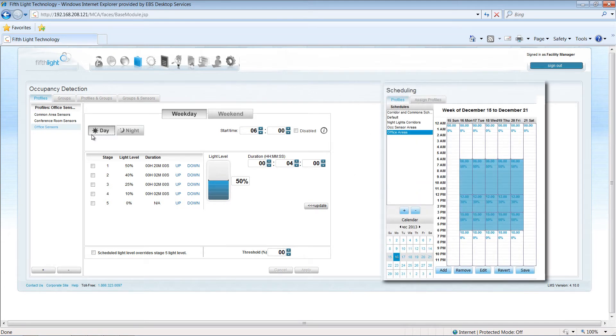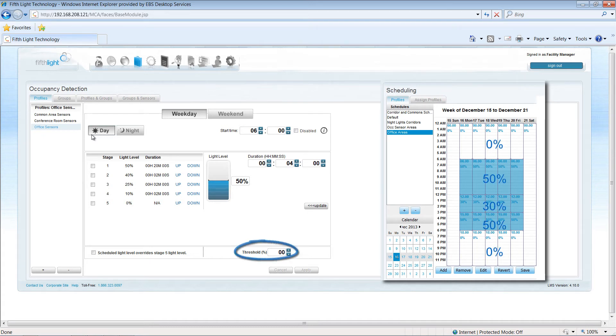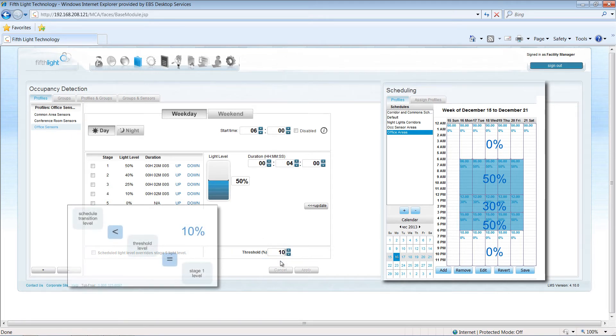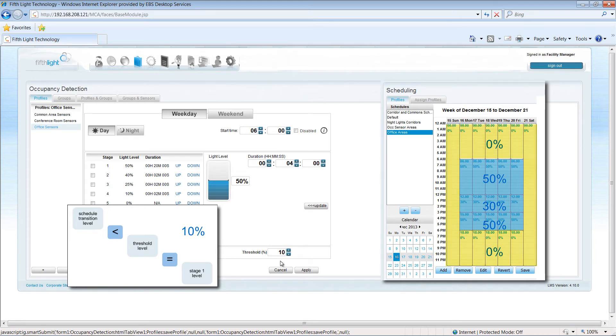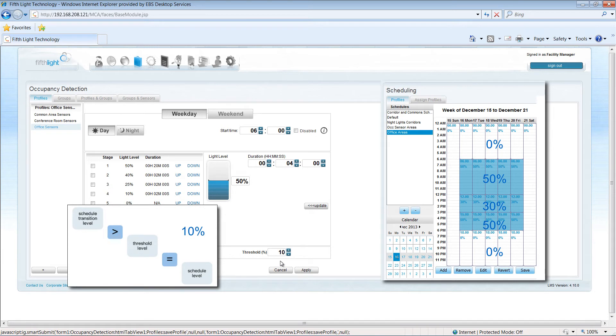First, I'll define a schedule profile with these transitions, and then I'll use my threshold field to create these dynamic changes. With my threshold at 10%, my Stage 1 light level will only be issued if the schedule transition level is below this, such as what I have programmed on the nights and weekends. If my schedule transition level is higher than the threshold, the occupancy sensor triggers the scheduled light level instead of the Stage 1 level.